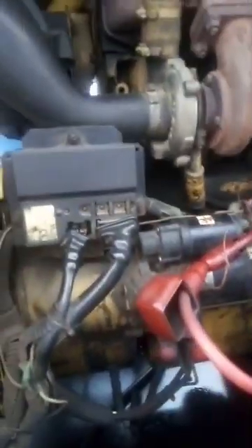We discussed some time ago, we talked about the MPU. You have the magnetic pickup, as you can see from here. It actually determines the position of the engine. Is the engine running? Is it stopped? So once the engine begins to roll, as commanded by the starter motor, the magnetic pickup will sense it and send the command to the module that the engine is rolling. You need to open up the fuel for this engine to run. So most times it can cause the engine not to start if it's faulty, because it will not actually know that the engine is cranking.